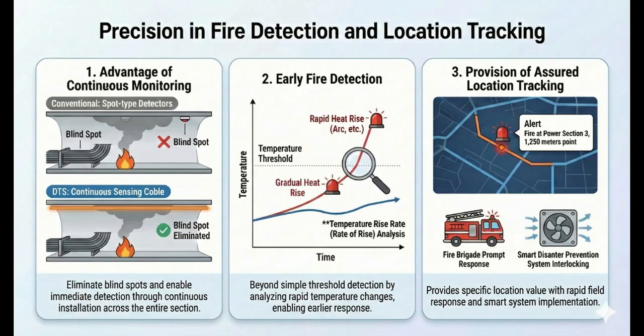First, continuous monitoring across the entire route eliminates blind spots and prevents missed risks. Second, instead of relying only on fixed thresholds, it analyzes temperature rise rates to detect early anomalies faster. Third, it provides accurate location information down to a specific meter point, which accelerates dispatch and inspection and enables smart integration with ventilation and fire protection systems.